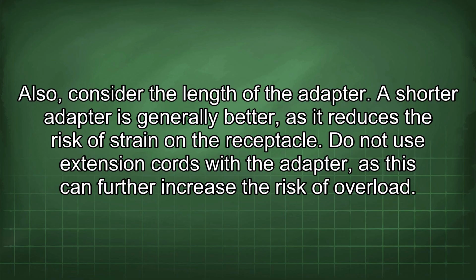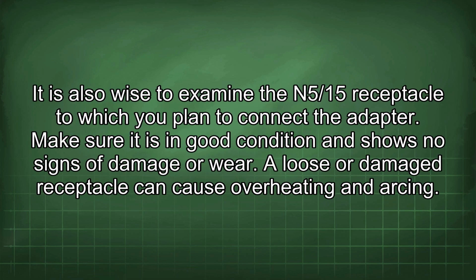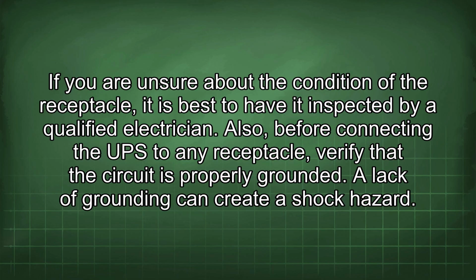Also, consider the length of the adapter. A shorter adapter is generally better, as it reduces the risk of strain on the receptacle. Do not use extension cords with the adapter, as this can further increase the risk of overload. It is also wise to examine the N5/15 receptacle to which you plan to connect the adapter. Make sure it is in good condition and shows no signs of damage or wear. A loose or damaged receptacle can cause overheating and arcing.